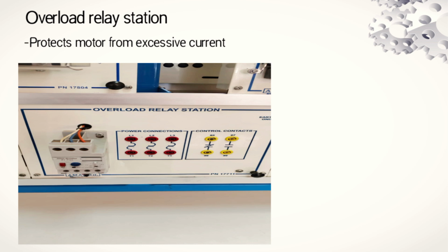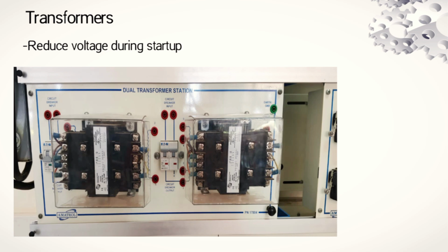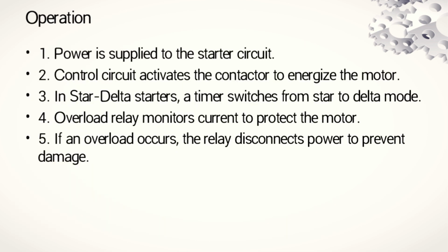the motor control circuit. Another component we have in the motor control circuit is the transformers. The transformers reduce voltage during startup. That basically means that the transformer we have in the circuit is a step-down transformer, since it reduces the voltage during startup. And then moving on to the operation of the motor circuit.